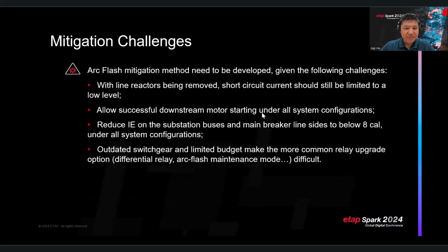So here we're providing our solutions, and here are the main mitigation challenges we have. The first one is that with the line reactors being removed, we still want the short circuit to maintain the lower level as before to protect the old switchgear equipment. The second one is that we should allow successful downstream motor starting under all system configurations. The third one is that we want to reduce the IE on the substation and its main breaker line side to below 8 calories under all system configurations per client standard.